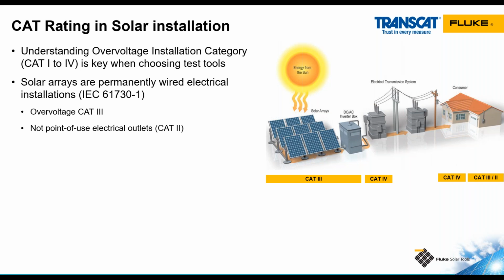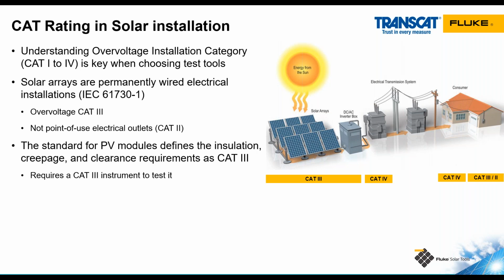So when you look at these systems, and our solar arrays, according to this IEC standard, are considered a category 3 environment, unlike our branch circuits in our house, which would be considered category 2 environments. We also have a category 4 environment where we get closer to the utility. That would be our point of interconnection with our PV array. If you're on the utility scale projects, between the inverter and the medium voltage transformer would be considered category 4 environments.